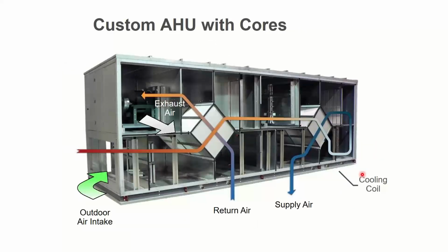In this case, I have two ERVs. It could be two wheels or it could be two cores like I'm showing here. It doesn't matter. It works the same way. One of them is treating outside air. One of them is a reheat wheel or reheat core in this case. So return air comes in, does this heat exchange with the outside air coming in, the dirty air molecule exhausts. I think we got that part.